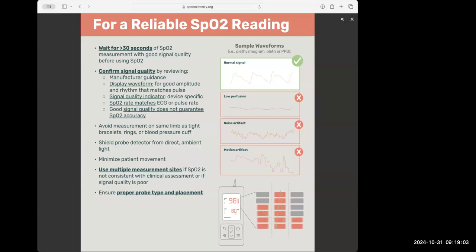Yeah, and each manufacturer tackles the PPG output for signal quality differently, both in a metric as well as in a bar display. Can the standard modify its language? I think I provided this feedback already, but can the standard modify its language to require user testing of what is considered to be an intuitive alarm for inadequate signal?